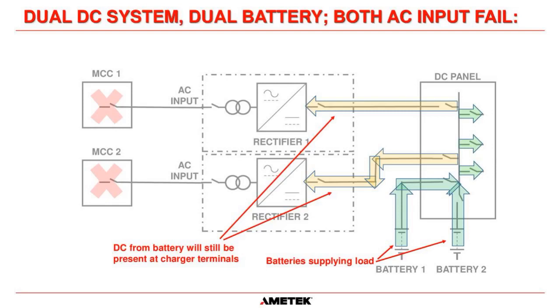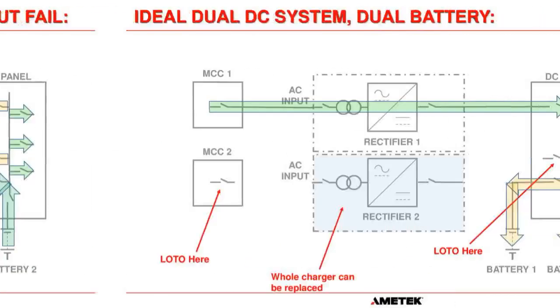Okay, and let me just check here. Somebody did type in a question: is it better for the batteries to be one string or two? It's always better if you have two strings of batteries, because that allows you to do maintenance on one string or replace one string, and the disconnects give you the ability to do that once the system is in the plant and up and running. This is all about maintenance once the system is installed, and it's always better to have two separate parallel strings. So thanks for that question.